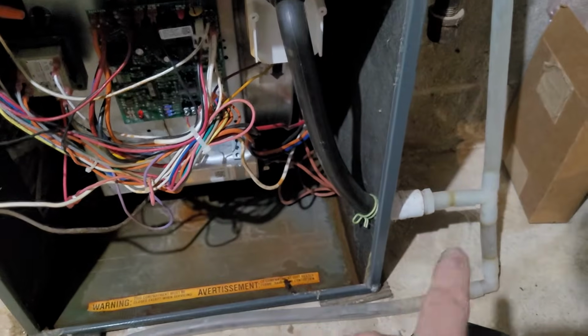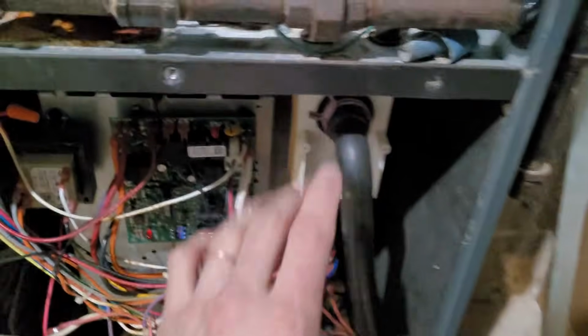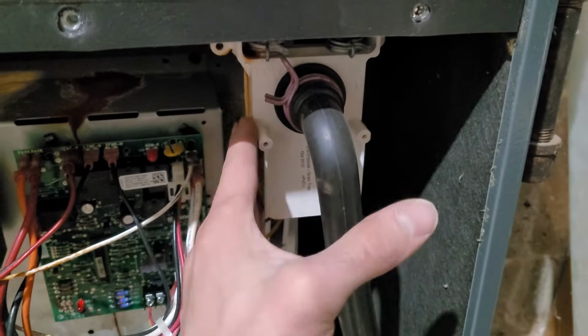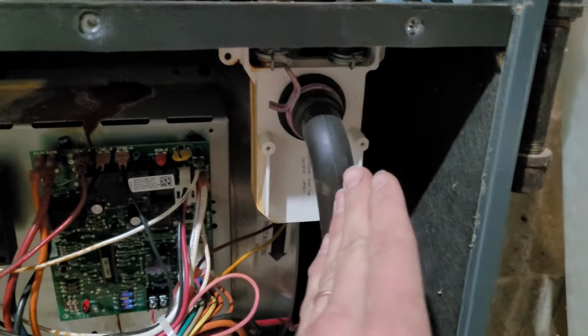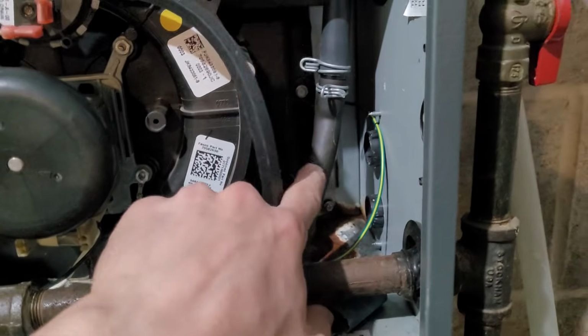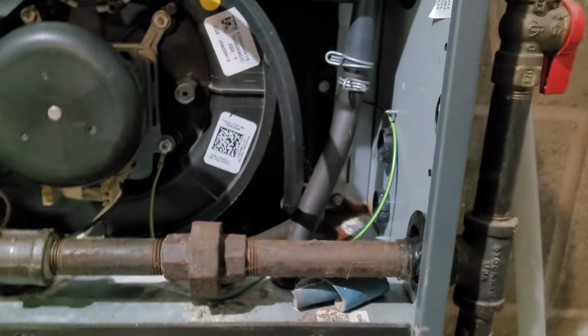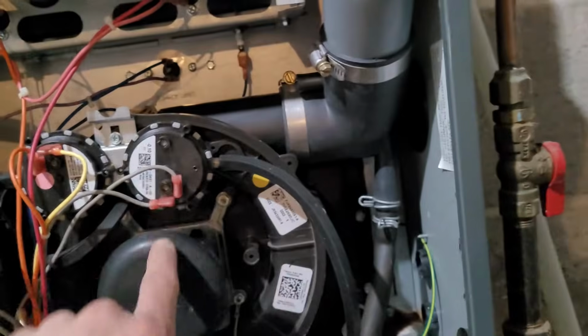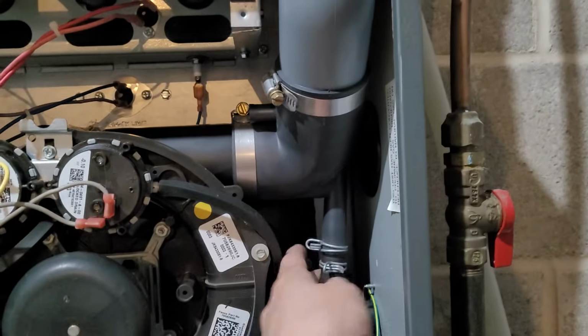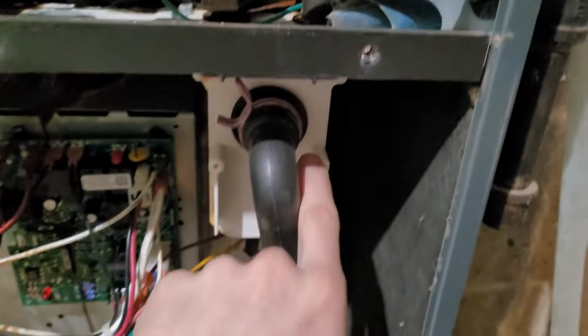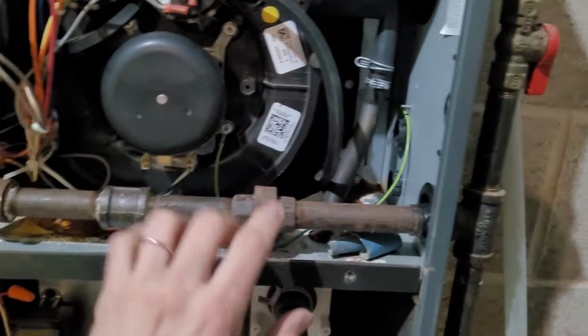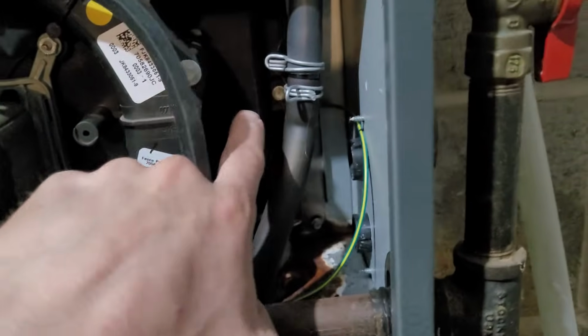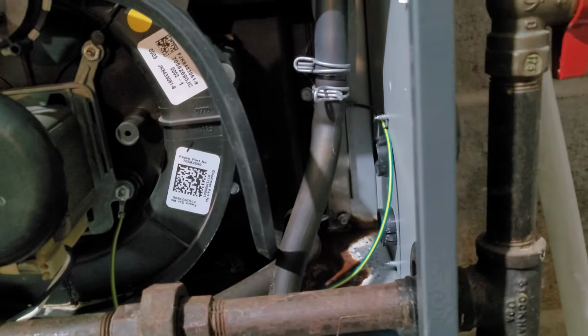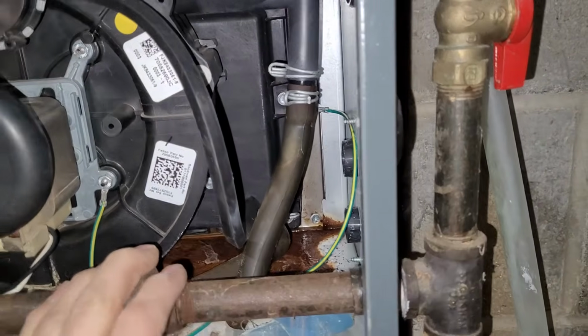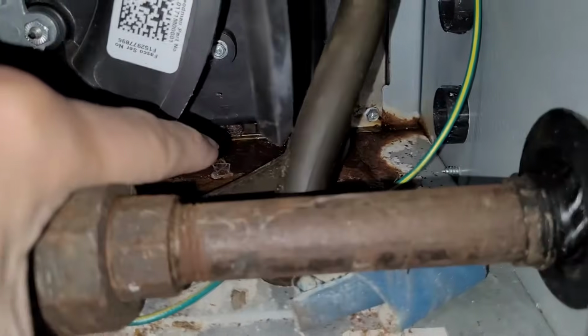So the way that these furnaces are set up varies quite a bit, but you're going to have some sort of condensate trap. Sometimes it's located in the blower compartment like it is on this Goodman furnace. Sometimes it's actually built into the collector box up in here. But you're going to want to look at all of your drain tubing. So your exhaust gas is going out right here, and that comes down and drains straight into the trap. That's where most of the water comes from. A lot of it then also comes from the collector box on the secondary heat exchanger, because that's where the exhaust gas is getting cooled down the most. Now you can see where this one's actually leaking. I'll talk more about that in a minute, but first we'll go over the tubing.